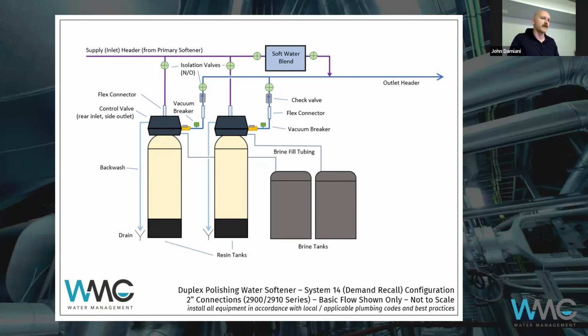the reason for that being you can't feed 100% soft water, zero hardness, to a cooling tower. This has to do with the saturation index that you're achieving on the tower. If you have zero hardness, the water is a little bit too corrosive, actually very, very much so, where you'll create a corrosion problem by solving your scale problem. So you do need a little bit of hardness in the system, and a blending apparatus will allow you to bleed the correct amount of hard water back into the system. And basically what that allows you to do is, let's call it, double your cycles.